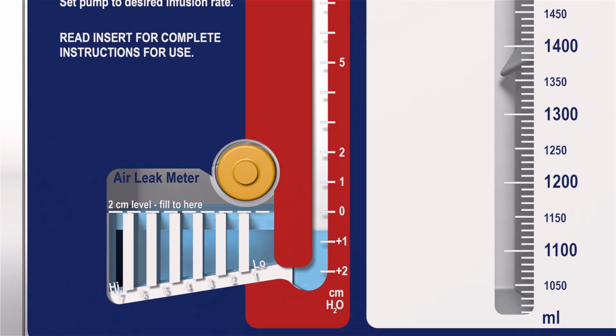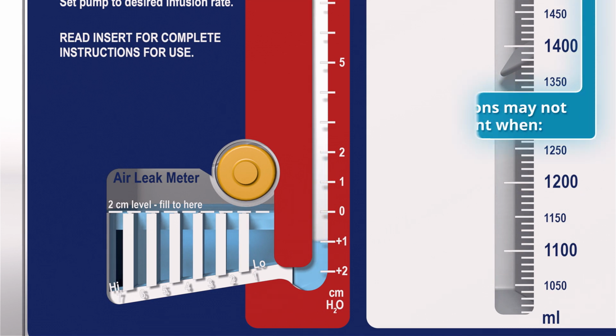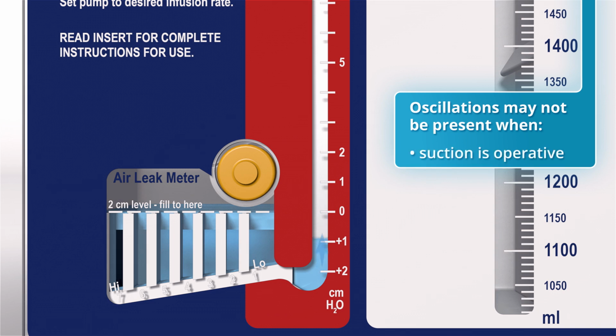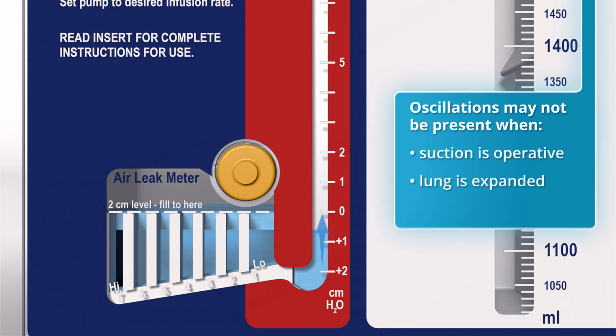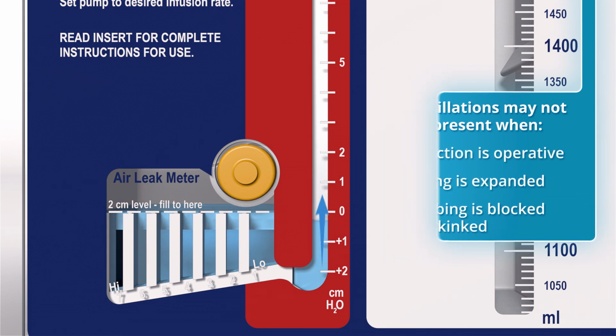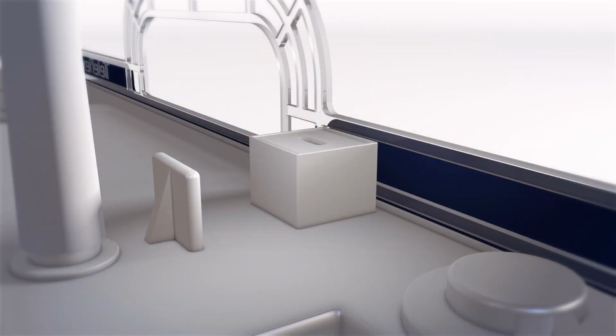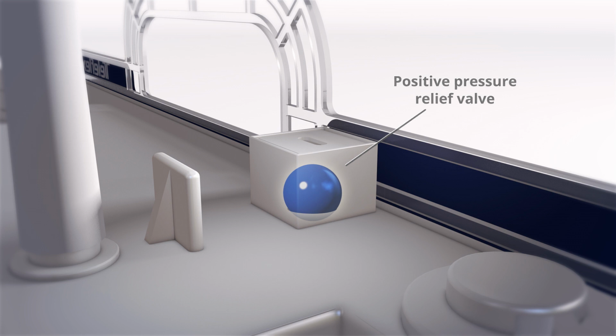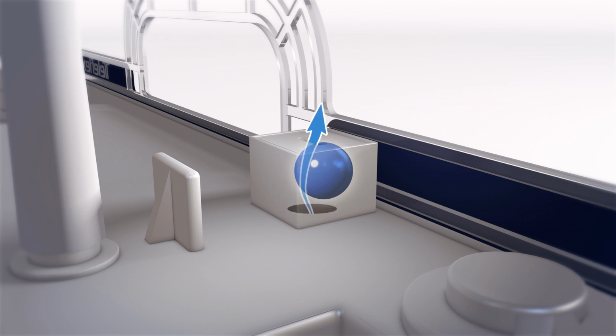Patency of the patient tubing may be observed as oscillation in the water seal chamber. Oscillations may not be present when the suction is operative, when the lung is expanded, or when the tubing is blocked or kinked. On the top of the unit above the water seal is the positive pressure relief valve. If suction tubing is blocked or occluded in any way, this valve provides a backup for air to exit from the Pleur-evac unit.